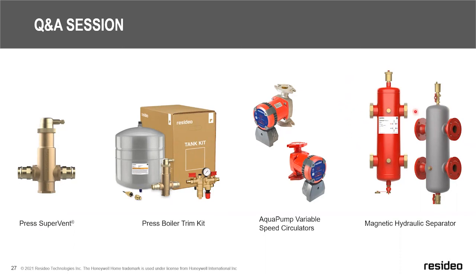But if you're using the outlet going to the system, different examples could come into different criteria. So let's say we've got 6 pumps on there. Each one's doing 2 gallons a minute. Well, now we're up into 12 gallons a minute. So yeah, you're going to want to jump up to 1.25 inches here. If you've got some of these monster houses like I've seen, sometimes that can lead to even 2 sizes jump. So it kind of varies.